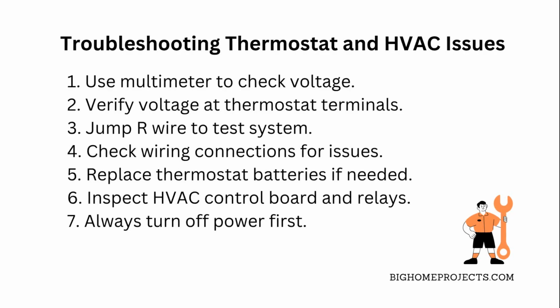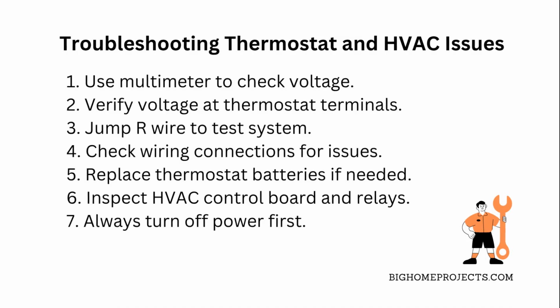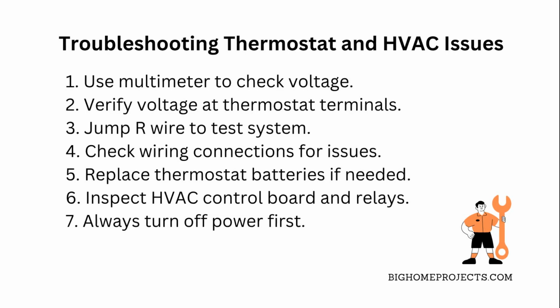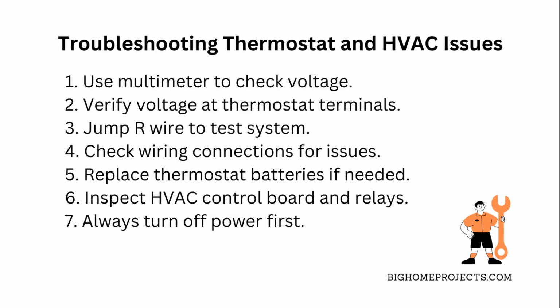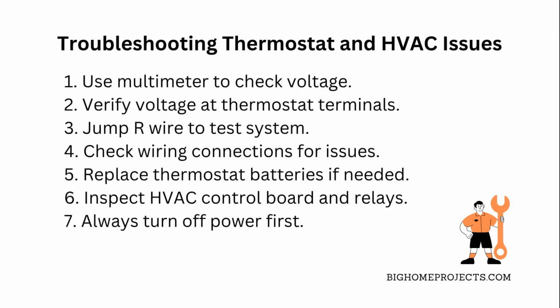Next, peek at the voltage at the thermostat terminals. No voltage means the thermostat might be dead. Try jumping the R wire to other terminals like Y or W to see if the system responds. This bypasses the thermostat, so if your heat or AC kicks in, you know the thermostat is the issue.